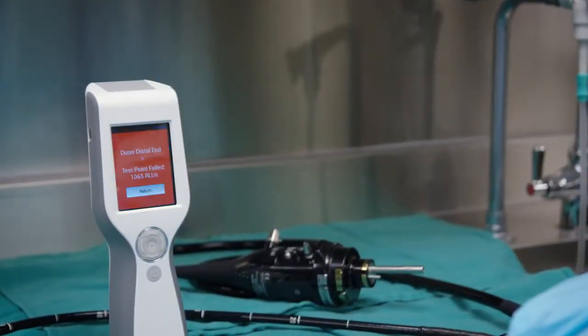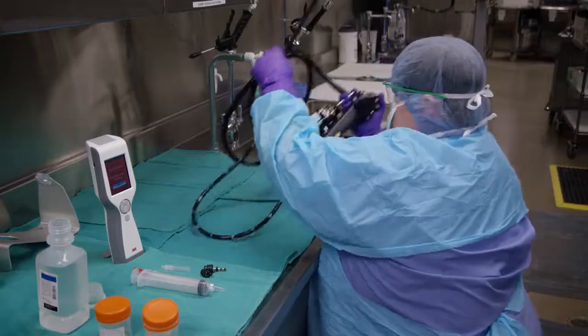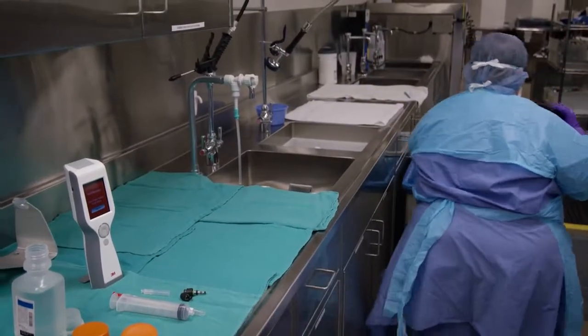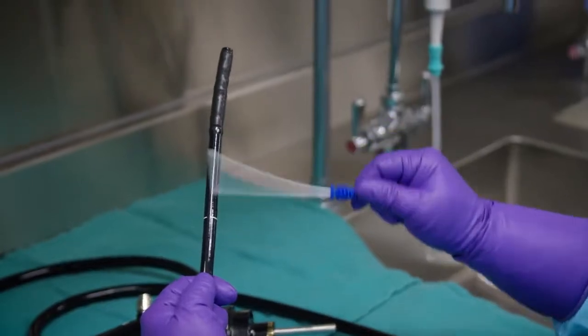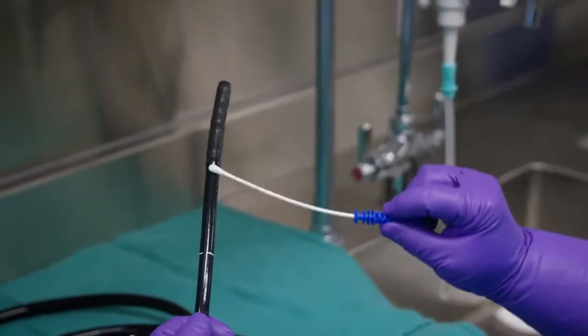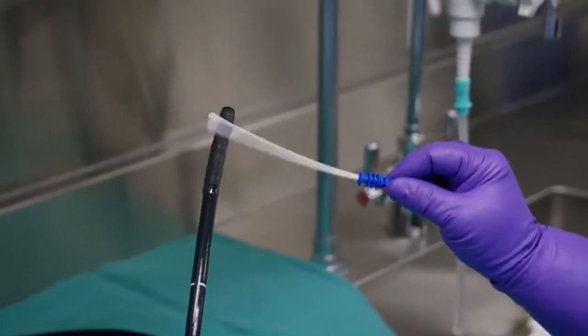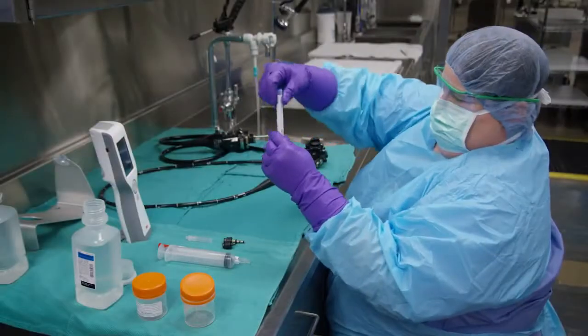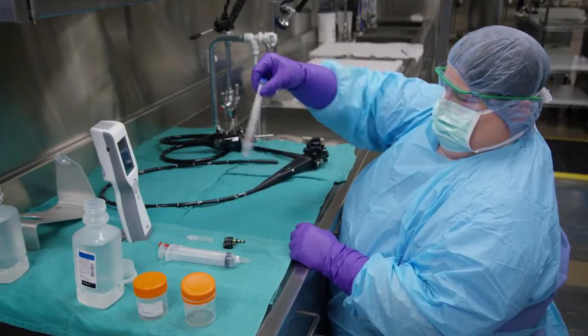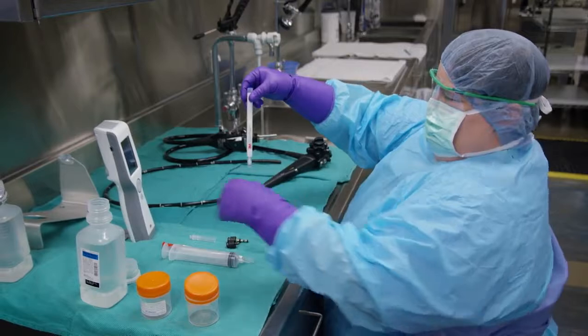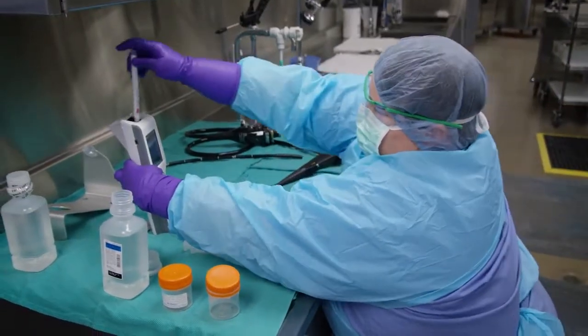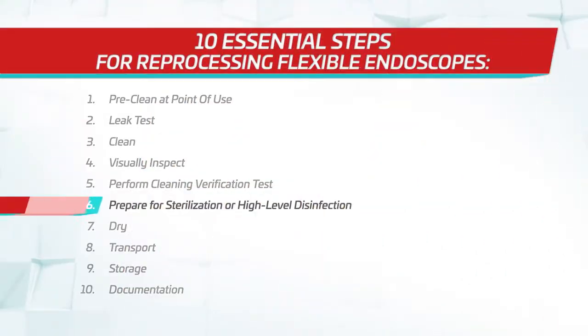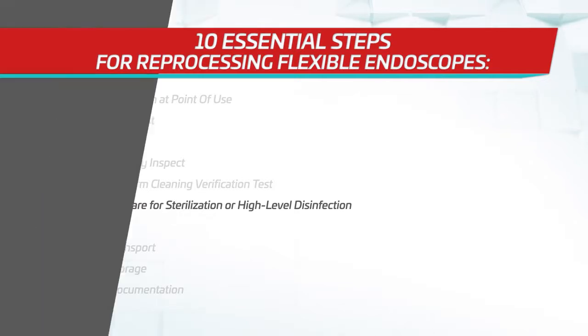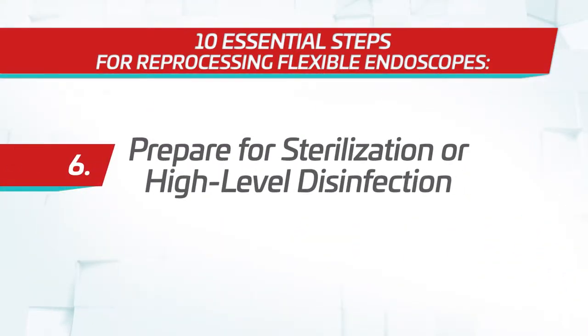If results show the endoscope is still dirty, document the results, then re-clean it right away and repeat the cleaning verification test to ensure the contamination has been removed. If the endoscope fails the test a second time, then it may be damaged. Document the result and tag the endoscope for repair.